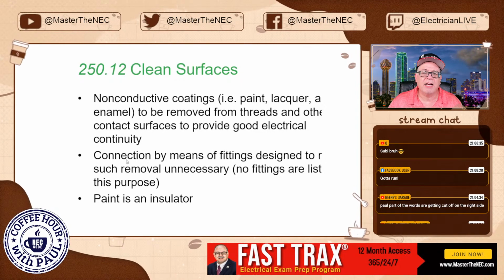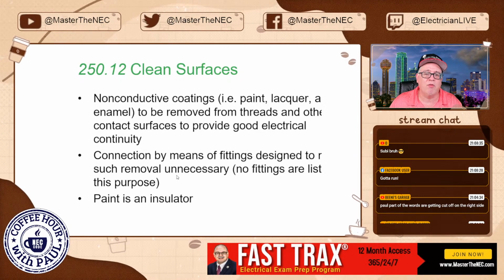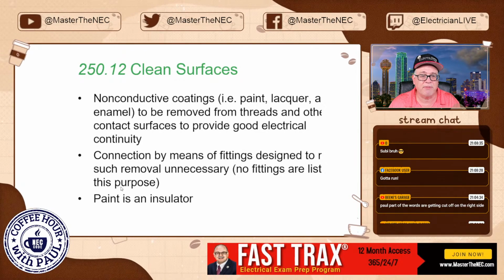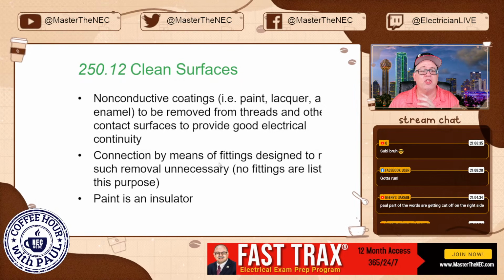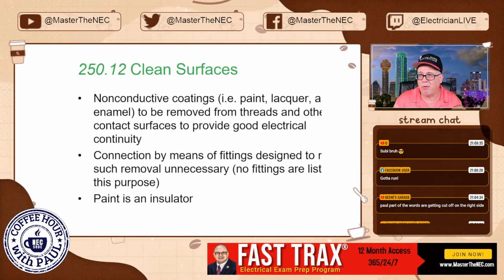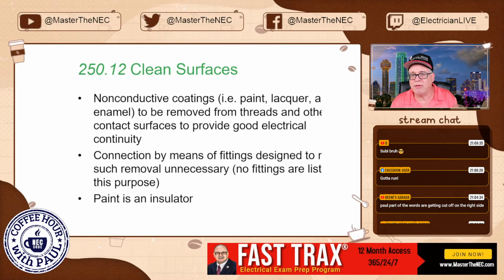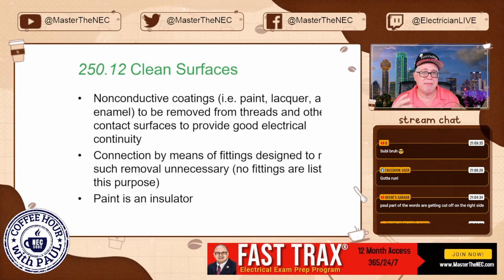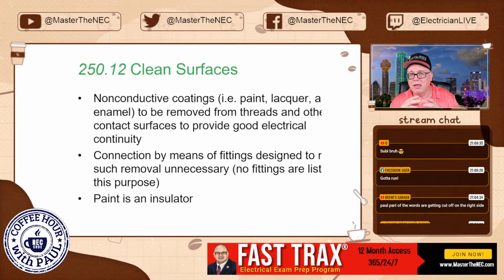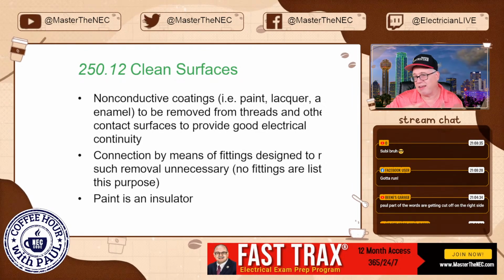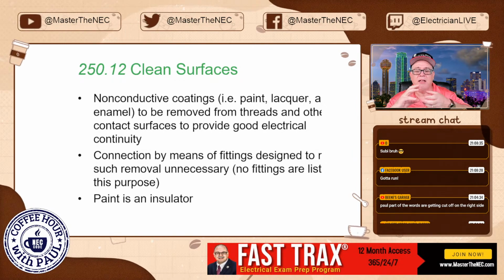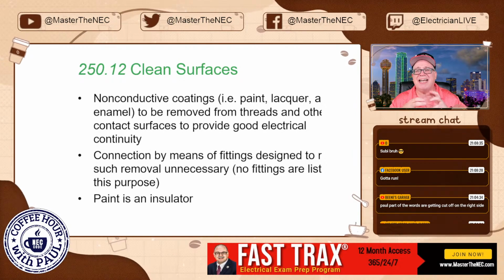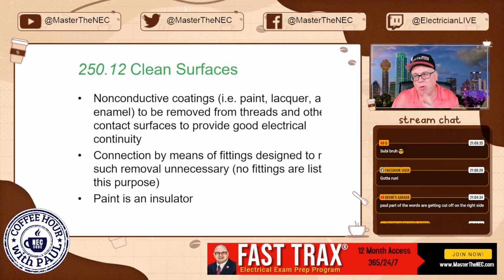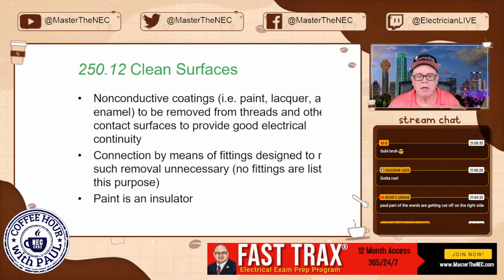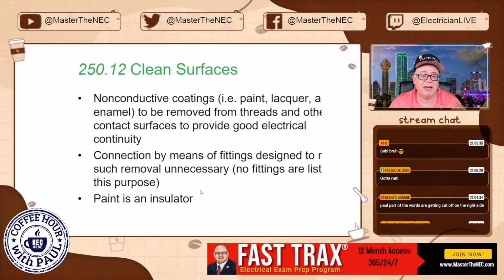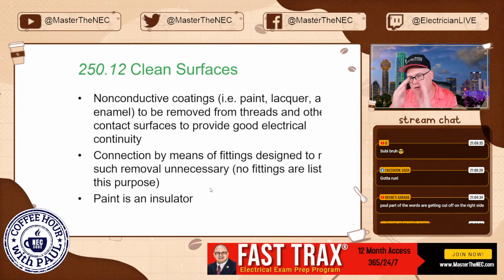Now, connection by means of fittings designed to make such removal unnecessary. No fittings are listed for this purpose, by the way, but if somebody comes up with one that says, okay, well, you don't need to, then you can get away with it. But I will tell you that you can make metal-to-metal connection, and you have a lock nut, and if you're doing rigid, for example, and you're doing, say, feeder applications, not at service, but feeder applications, then you can get lock nuts that will bite into the metal, that type of thing. And it will be evident when that happens. Okay. And of course, paint is an insulator. We need to make sure that we're going to ensure the integrity of these connections.